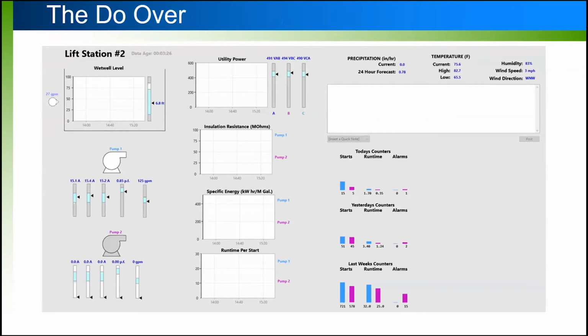So if I had a chance to do this over again, I would do something a bit more like this. I would not just show the wet well level, I would trend it and show you where the wet well's been over the last period of time. Graphing utility power: a lot of times the root cause of a lot of problems at lift stations can be tied back to utility power. So this RTU was able to track that, but we weren't showing that on that initial screen. Another thing it can do is take automatic insulation resistance tests, so automatic Megger tests for your pumps. But that wasn't being shown on that initial screen either. You had to go search for it.